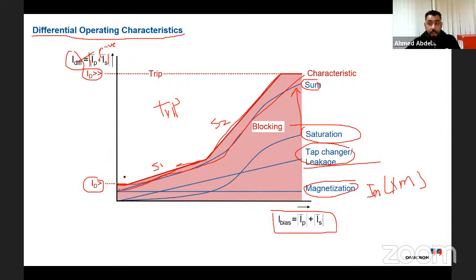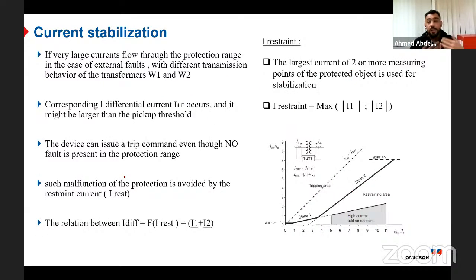How can I see this? For example, I define here one of the most famous relay manufacturers. This is from Siemens. So I need to assume this case to define the characteristic. I need to assume that I have a very large current through the protected object. Then this will cause a differential current, W1 and W2. Then I correspond to the differential current IDIF. So I will calculate the minimum operating current.